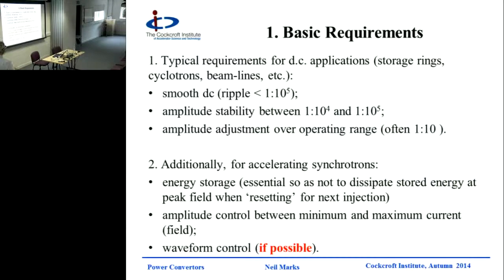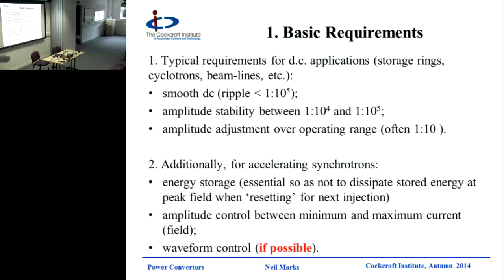And then for synchrotrons, where we are oscillating and changing the field level in the dipoles and in the quadrupoles, we need to have energy storage, because when the magnets have got high flux density, they've got energy - they're storing work - and when they come back down again, it's got to go somewhere. And then we need to control the amplitude between minimum and maximum current, which is the field. And if at all possible, in a cycling accelerator, it would be very nice to have control not just of the amplitude at the top and the bottom, but also of the waveform - where it goes from A to B. It's no good just knowing the way from London to Brighton; you need to know which route you take.